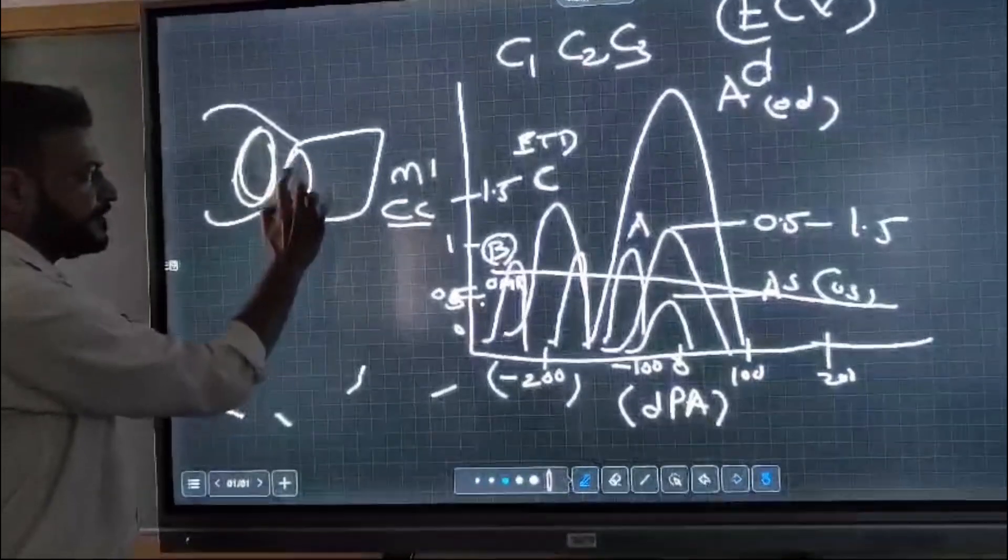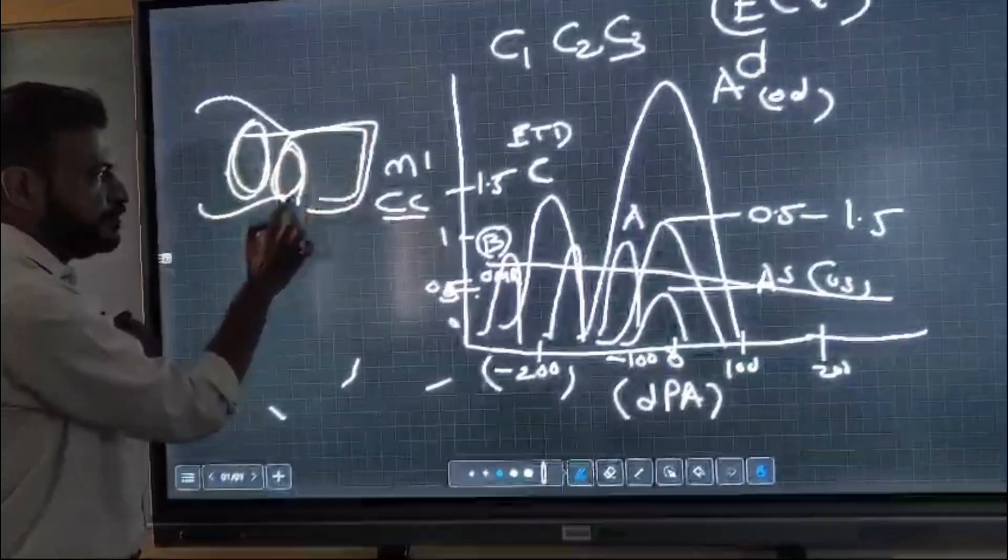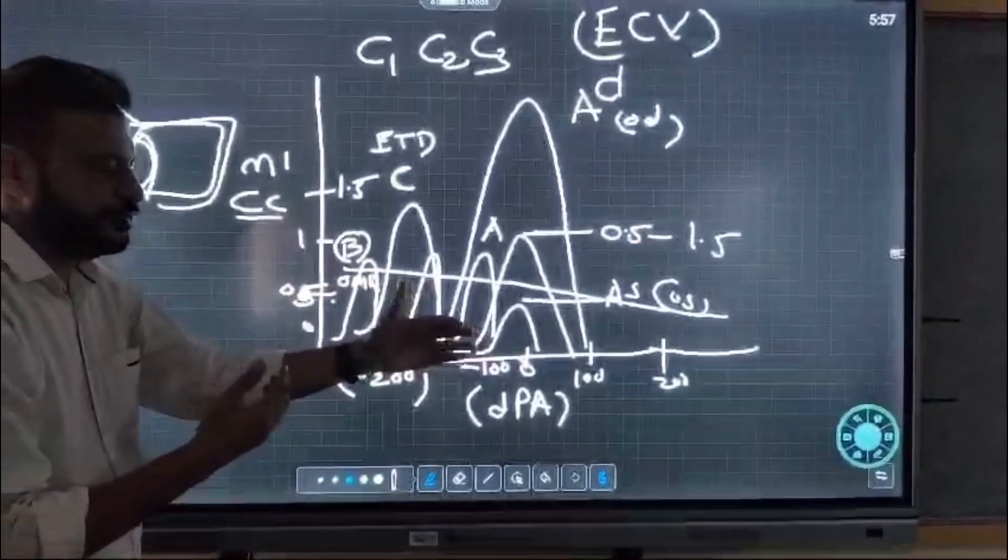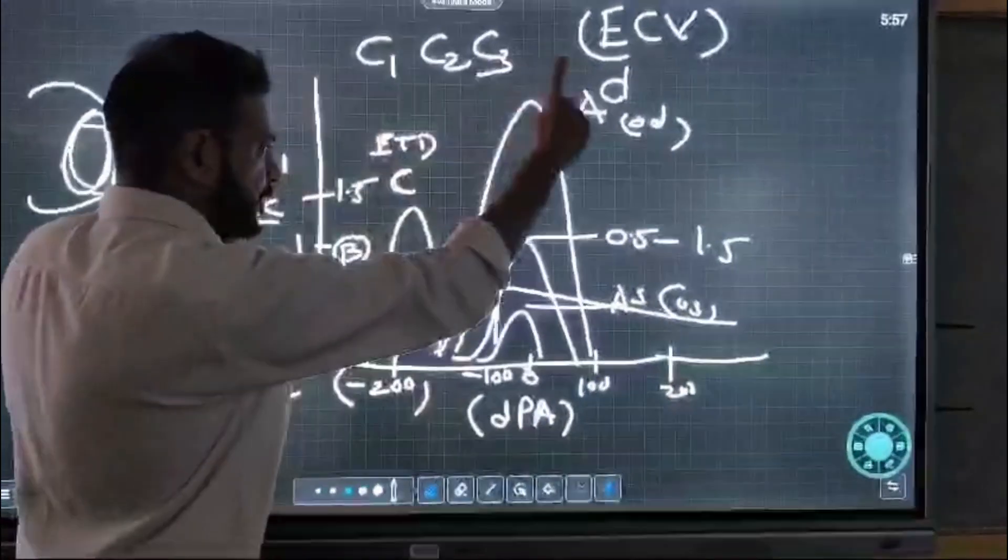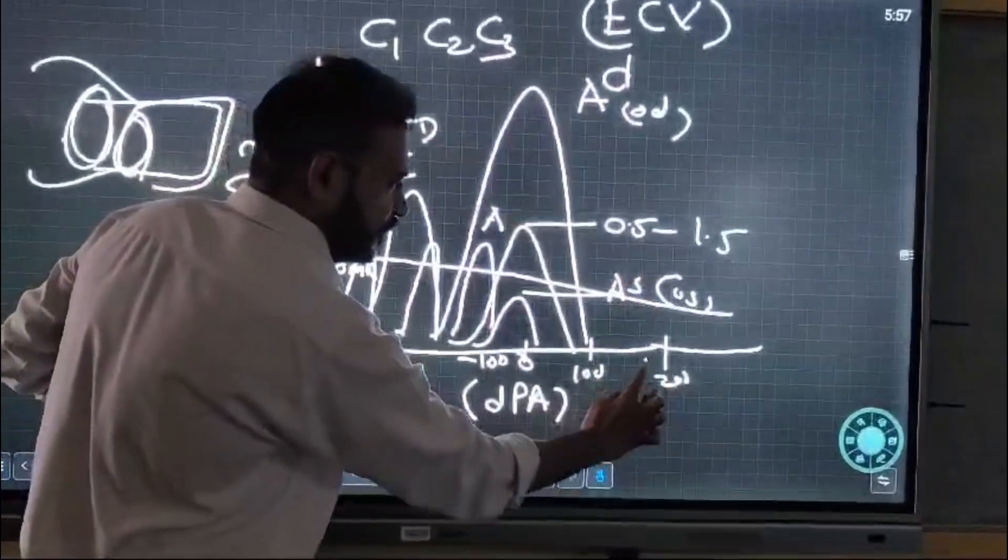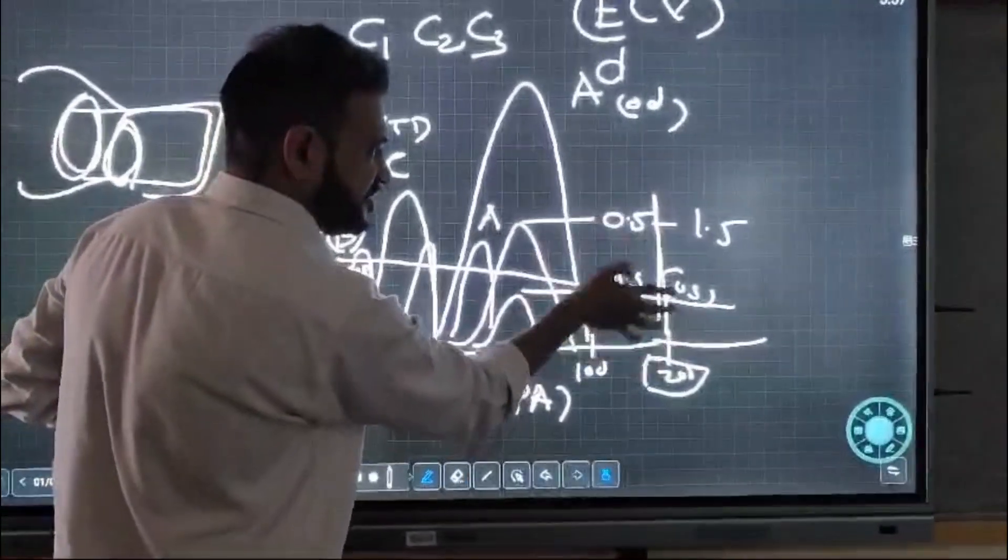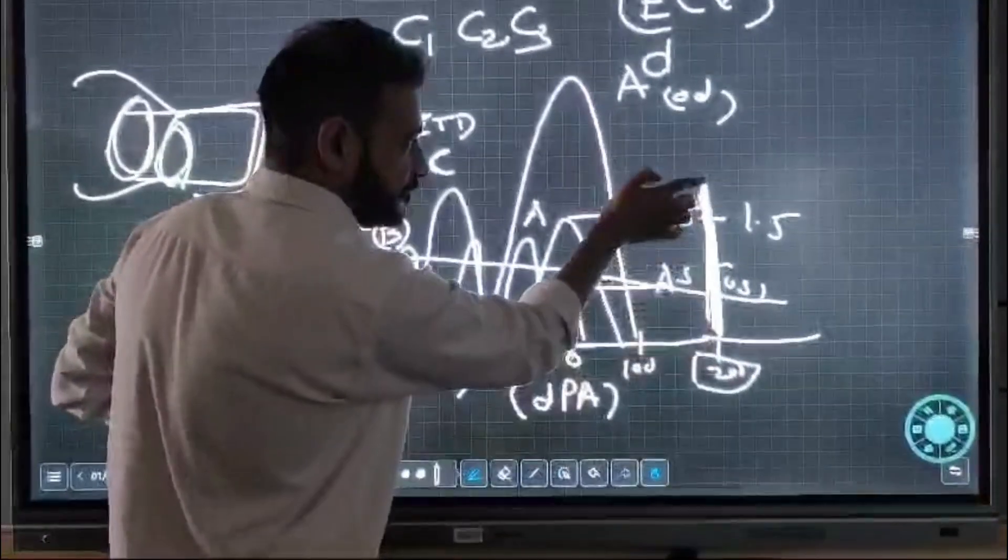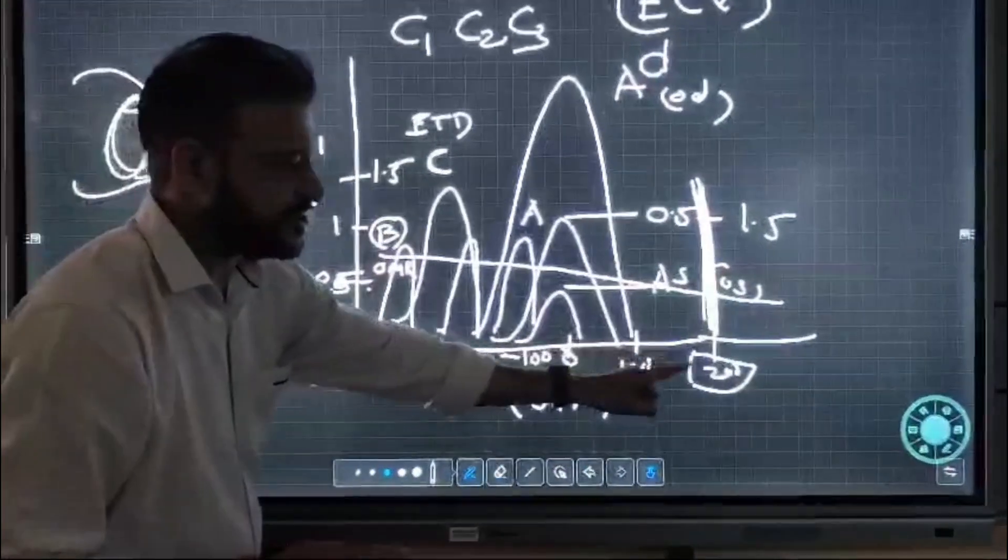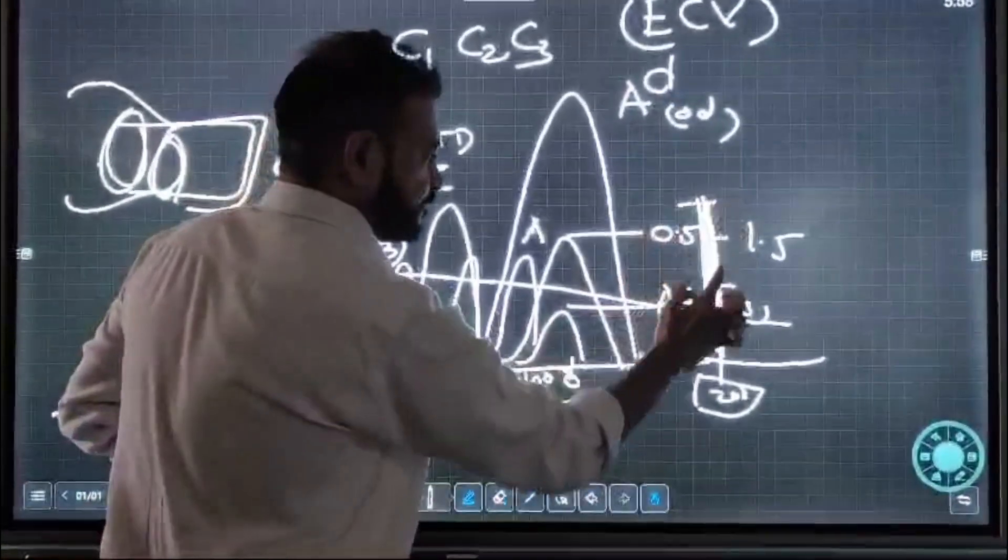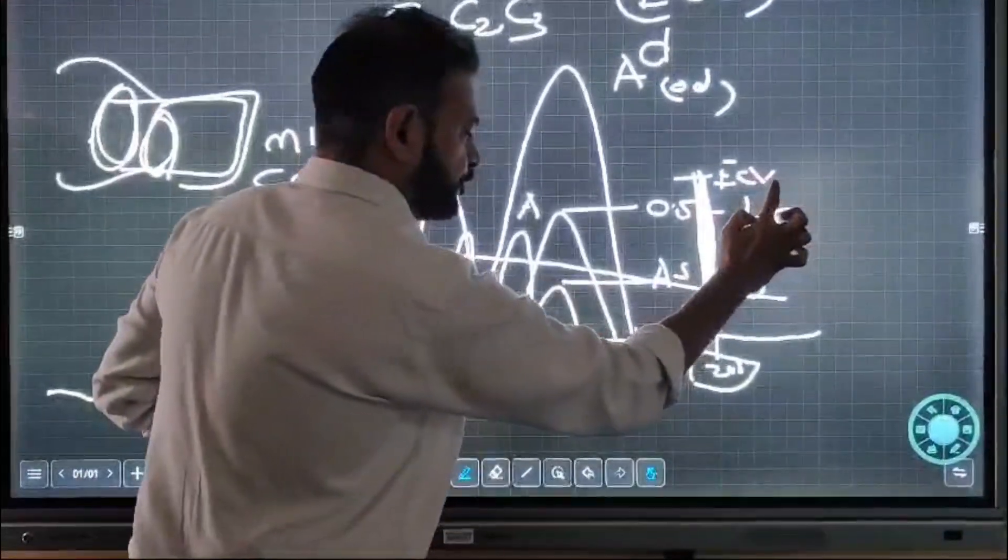If there is a perforation, the volume will be more. Where does a tympanogram show the volume? At the level of plus 200 decapascals, you will find a bar which shows the external canal volume.